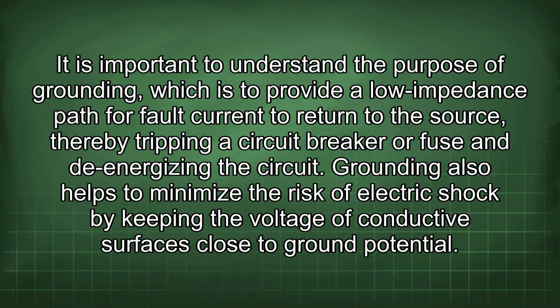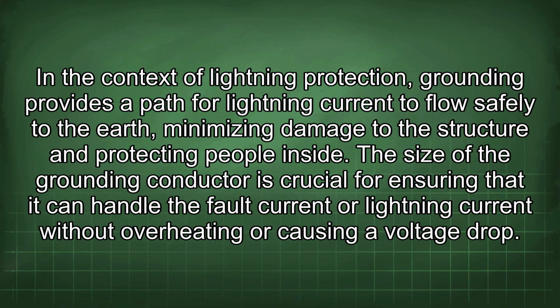It is important to understand the purpose of grounding, which is to provide a low impedance path for fault current to return to the source, thereby tripping a circuit breaker or fuse and de-energizing the circuit. Grounding also helps to minimize the risk of electric shock by keeping the voltage of conductive surfaces close to ground potential. In the context of lightning protection, grounding provides a path for lightning current to flow safely to the earth, minimizing damage to the structure and protecting people inside.